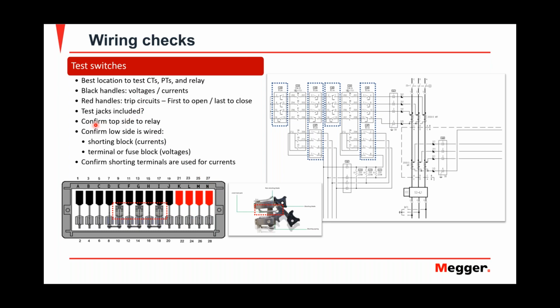Make sure that if you have test switches, that they have test jacks. Those are these guys right here on the red rectangle and right here. These are points of isolation. When you have a test paddle, you would put the test paddle and it will physically isolate the top points from the bottom points. On your currents, the currents will be short circuited by this test switch right here. The bottom handle, as it goes down, it shorts out the currents coming from the CTs on the bottom.